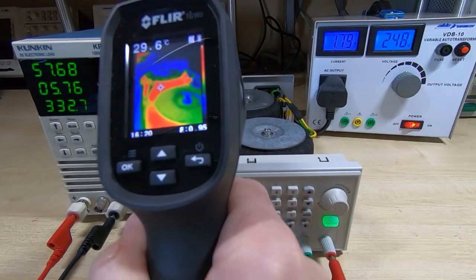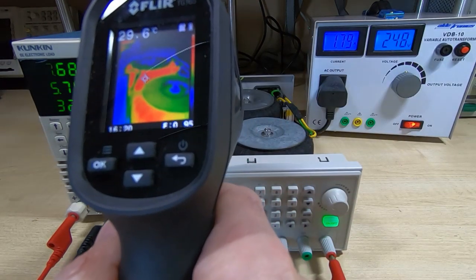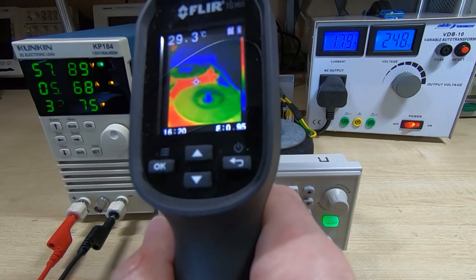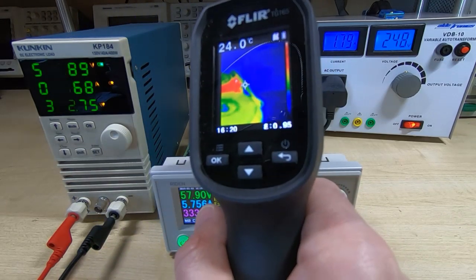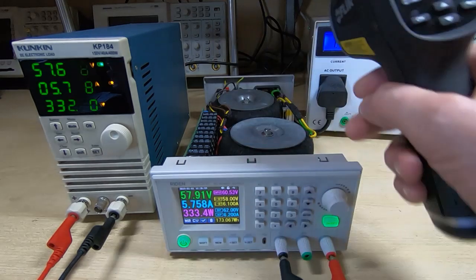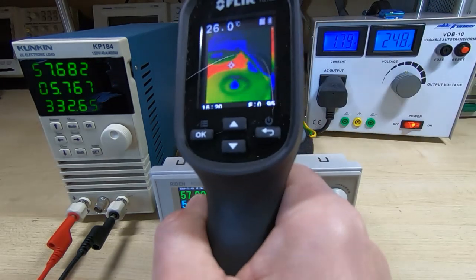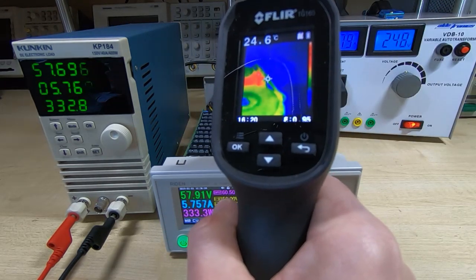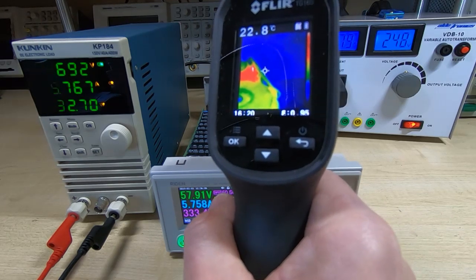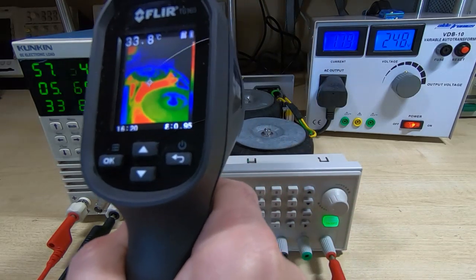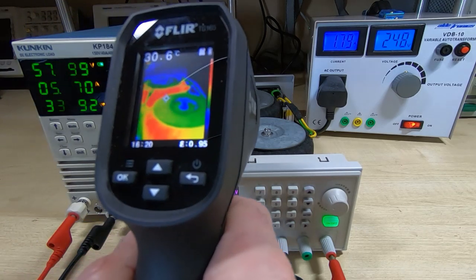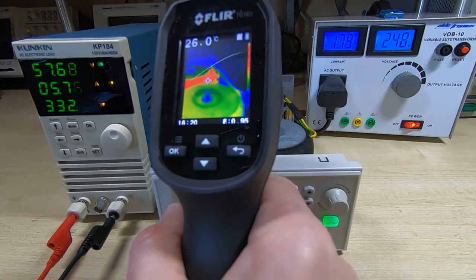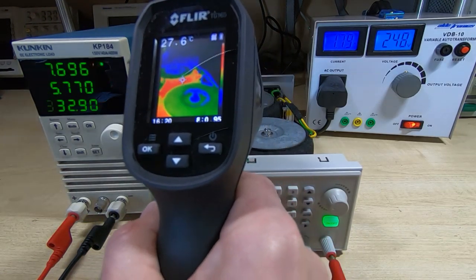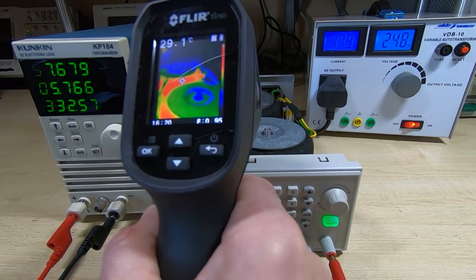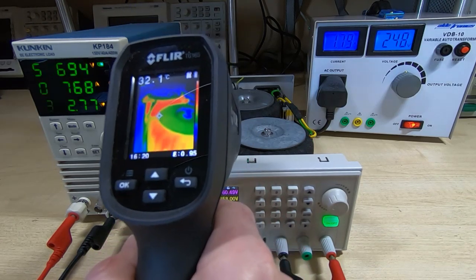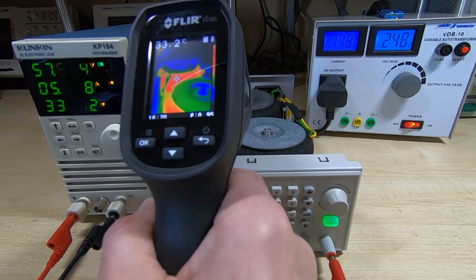Looking at it through the thermal camera now, it does appear things have heated up, but in reality certain parts have cooled down. The cables along this side that were glowing red before have now cooled because they're in the airstream, which makes other things look like they've heated up, since the temperature spread across the enclosure has dropped. But if you look at the actual temperatures displayed, they've actually gone down.